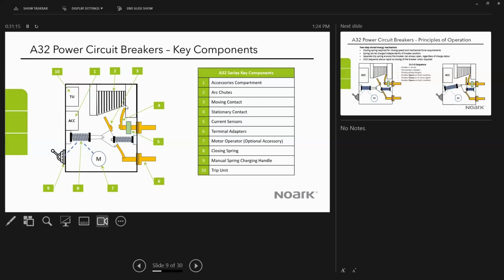Critical key components in the circuit breaker. If you view this from the front, you'll see that there's a place for accessories, and we'll be going into a lot more detail into what the accessories are. But functionally, inside the breaker, the primary components are the moving and stationary contacts. So these are the contacts that open and close the circuit. They're typically large copper formed contacts that open and close with the mechanism. The mechanism is driven by some very large springs. So you'll see when we get into the next couple of slides how they operate. So the contacts are operated by the springs.